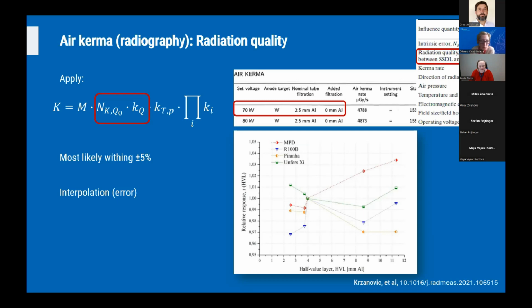Calibration factors are provided by secondary standard dosimetry laboratories for certain standard radiation qualities. However, in clinical conditions, these dosimeters or detectors are used in a range of different radiation qualities that are quite different from the standard radiation qualities. And the solution, most likely, and Stefan confirmed this today, is that the dosimeters would perform better than 5% uncertainty.